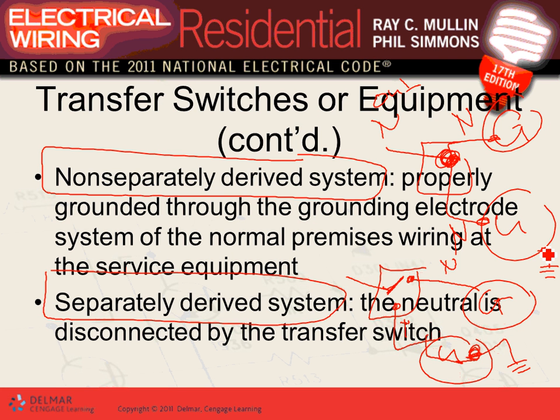Any comments, guys, about separately derived systems? Which one of them is better than the other? You can run any one of them. If your generator is 50 kW or less, you have to go separately derived system anyway, so you have to switch the neutral. If you switch the neutral, Derek, you're going to pay more money, because a three-pole auto transfer switch is more expensive than a two-pole auto transfer switch. So be aware of that.